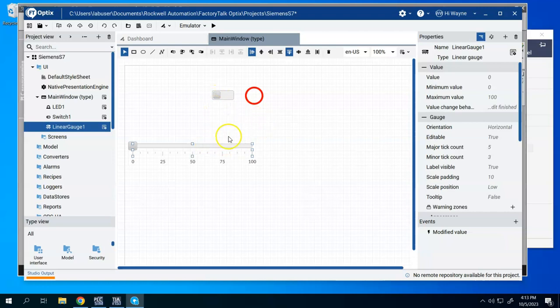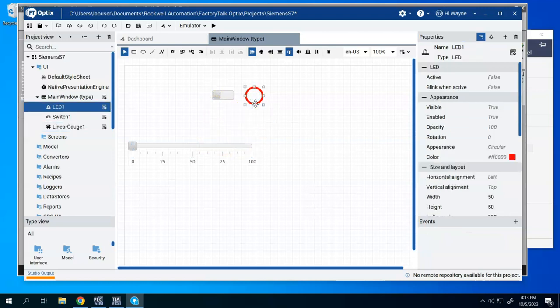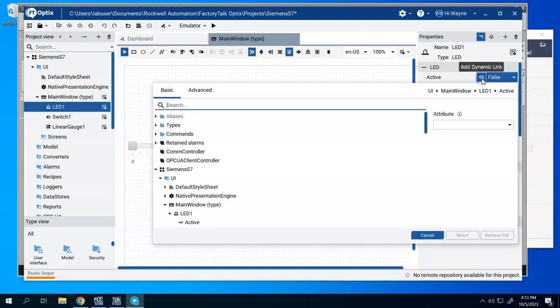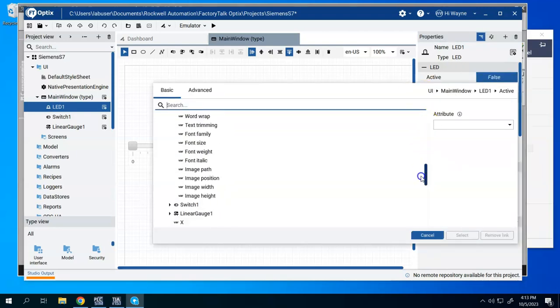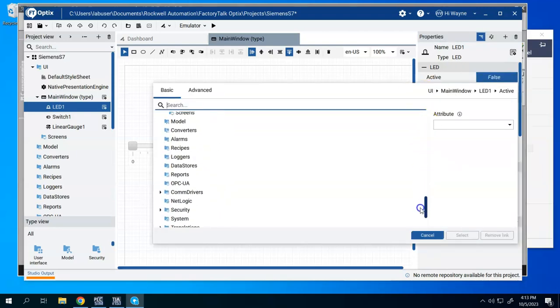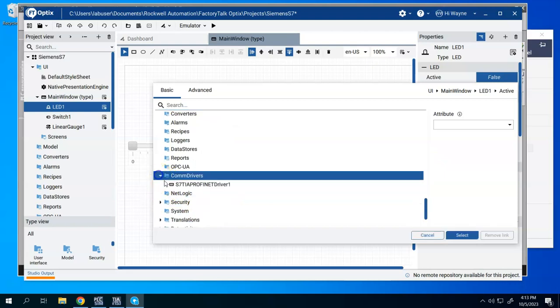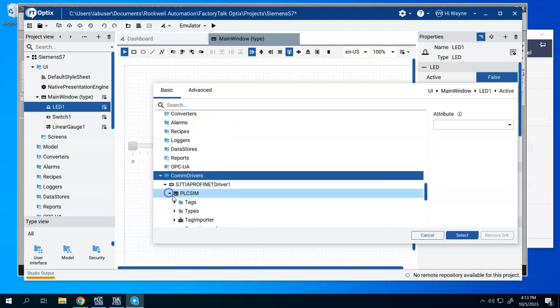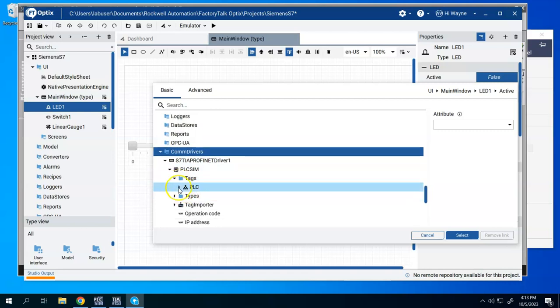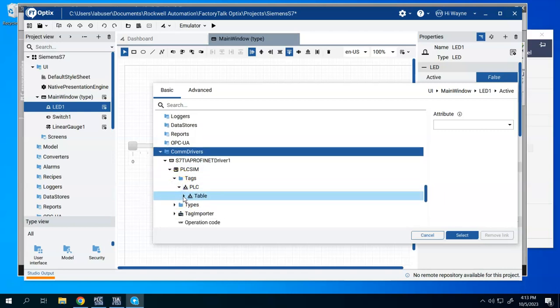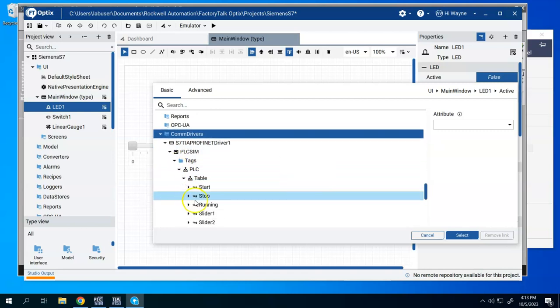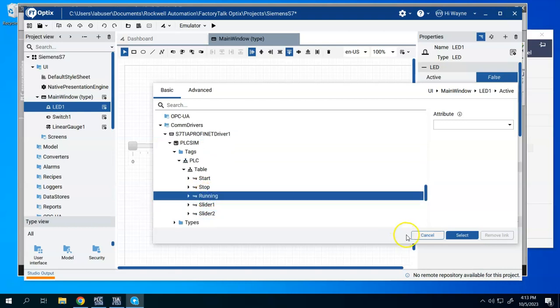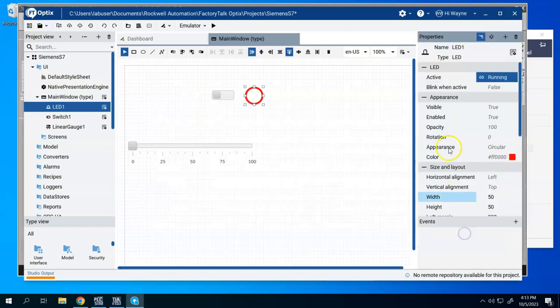Now I'm going to do a copy paste once I set these up just to save a few minutes. But we'll come to our LED first. I want it to be active. So to make it active, we can change this dynamic link. Click on this. We can scroll down until we get to our com drivers. Go to tags. PLC table. We're going to show this as running. That way that LED will light up when we're running.